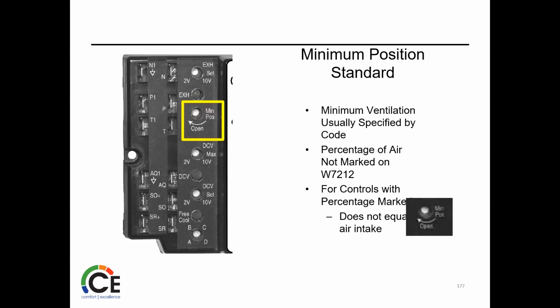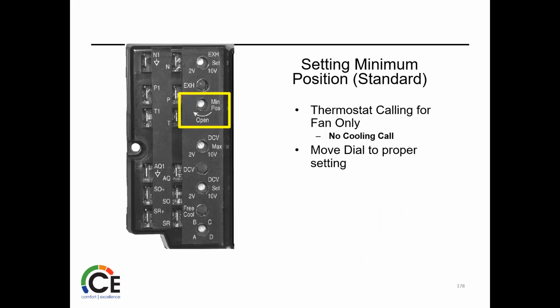Minimum ventilation is usually specified by code, or if you have an engineer, somebody somewhere should know. The percentage of air is not marked on this control. Even if it was, it doesn't really tell you the actual air intake, so you're going to have to work through that. So, thermostat calling for fan only, there's no cooling call, so we're setting minimum position at this point, if you can do it by hand. Damper movement from full open to closed should take about 2.5 minutes, so if you're looking for something instant, it's not going to happen. Change your minimum position.